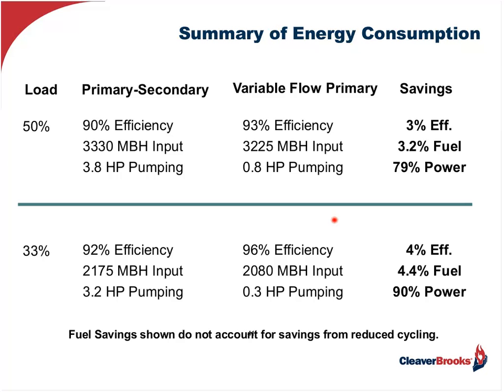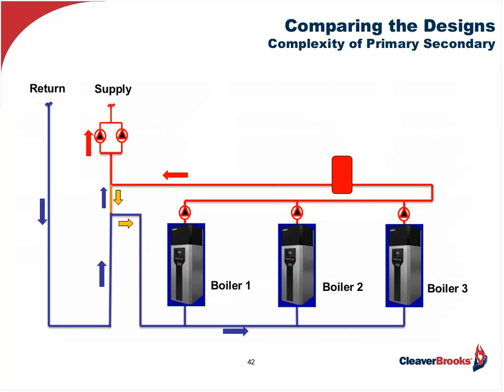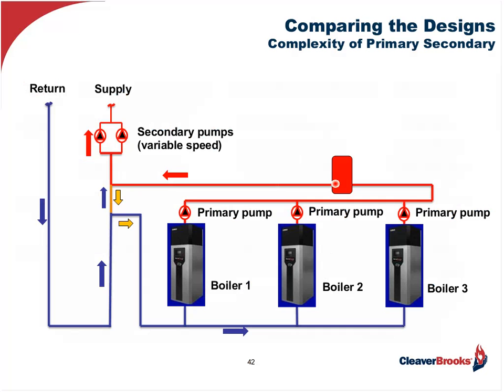Key takeaways here: in any scenario, we could have looked at any percentage we wanted to, and you would have seen the variable flow primary save energy both on boiler and pumps. Now, sometimes people talk about the complexity of variable primary pumping. Well, let's look at the complexity of primary-secondary. You have your system pumps, and you have your primary pumps. And remember, your primary pumps aren't just the pump. As I mentioned before, they're going to have a check valve or triple duty valve to prevent backflow through an off boiler. Typically, people put strainers on the pumps to protect them, and you have a starter of some sort.